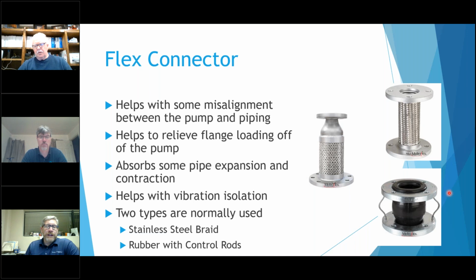There was a job I was on, and it was some cooling tower pumps, and when the pump turned on, that pipe jumped up, it seemed like a couple inches, but it was extremely noticeable. It was a 10-12 inch pipe, and I was a little scared to see that thing jump up there. But I do want to caution you when using these. The braiding here restricts it from pulling apart too far. So this braiding, this little braided wire, is really your control rod.